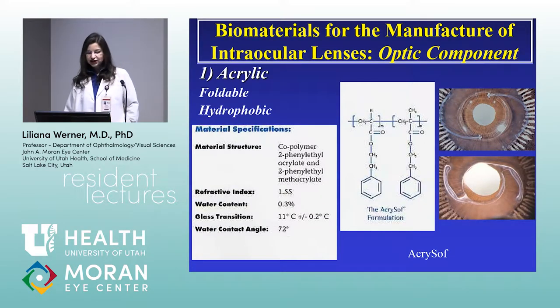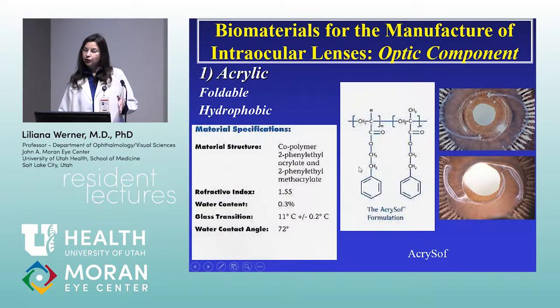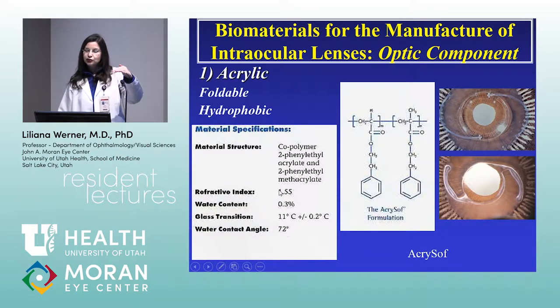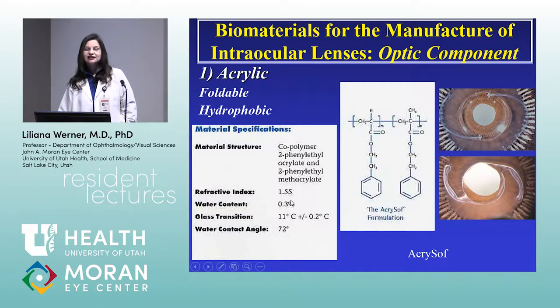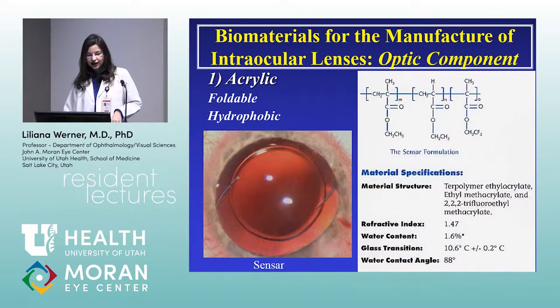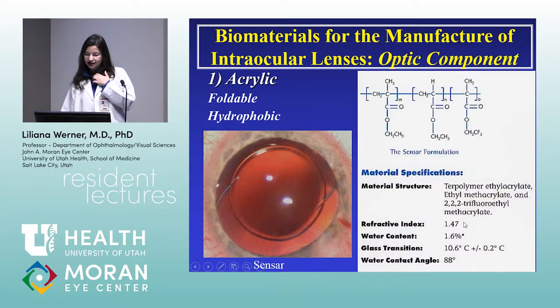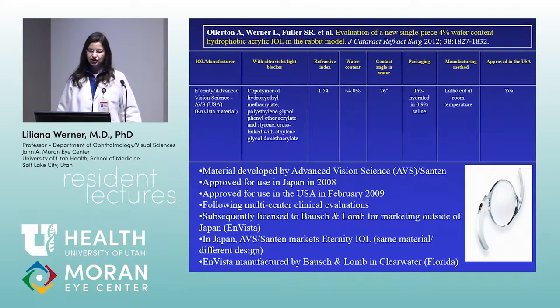Moving to hydrophobic acrylic materials — again, each lens in the market is very different. For example, the AcrySof material has a refractive index of 1.55, one of the highest, meaning for a given dioptric power it is the thinnest intraocular lens. Its water content is usually less than 0.5%. The Sensar material is used in the Tecnis lens by AMO, again with a much lower water content than hydrophilic acrylic materials.